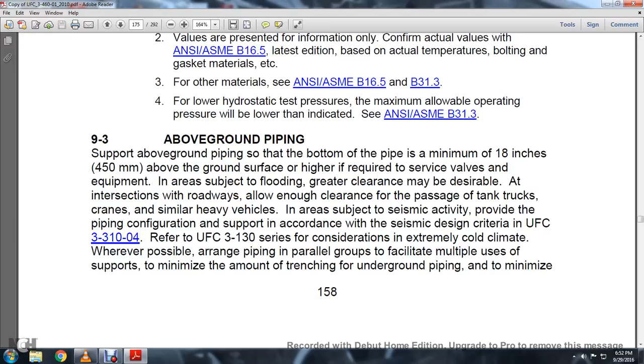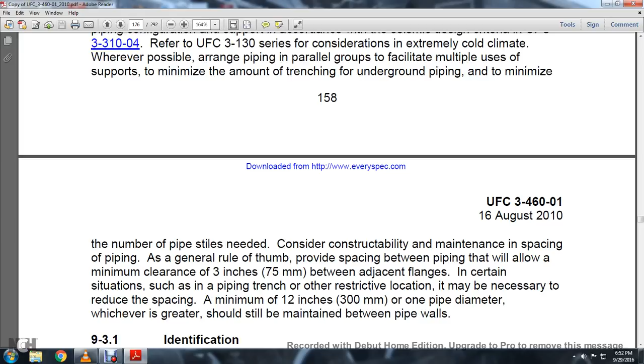Provide spacing between the piping that allows a minimum clearance of 3 inches between adjacent flanges. In certain situations, such as pipe trenches or other restrictive locations, it may be necessary to reduce the spacing to a minimum of 12 inches or one pipe diameter, whichever is greater, which should still be maintained between the pipe walls.